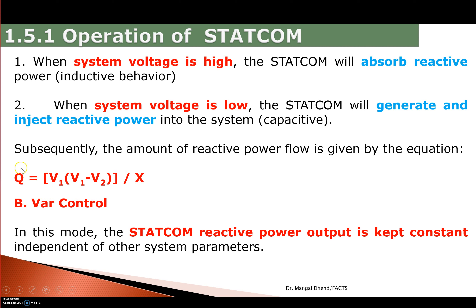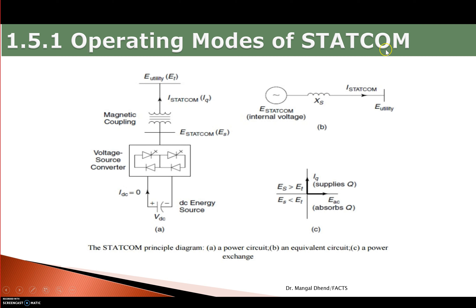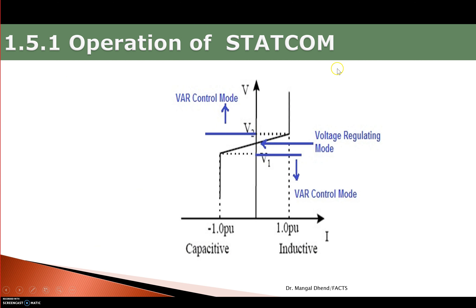For real power flow, the sine of delta (phase angle) term appears in the equation. In VAR control mode, STATCOM's reactive power output is kept constant, independent of system parameters. In voltage regulation mode: when ES > ET (V1 > V2), STATCOM supplies reactive power; when ES < ET (V1 < V2), it absorbs reactive power. These are the two operating modes of STATCOM, which we will further discuss in the next session.